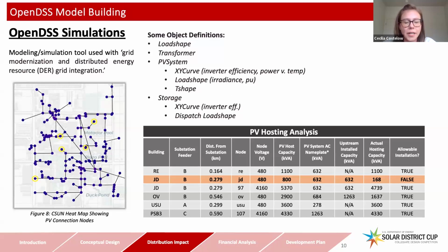We also did a PV hosting analysis to understand if we were violating thermal or voltage constraints. So you can see, for instance, we weren't able to connect our PV installation at Jacaranda Hall directly to that building due to the upstream PV installation at Redwood Hall. So for both Jacaranda Hall and parking structure B3, we connect at different nodes, 97 and 107 respectively, and we connect to those nodes at the feeder voltage of 4.16 kV through the installation of 2 new transformers. The figure on the left shows the nodes we're connecting at that are highlighted in yellow.